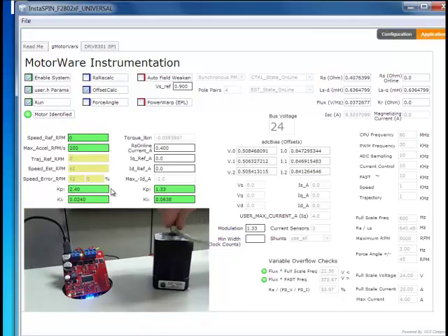At zero speed, you'll see that the motor isn't moving, or it's moving slightly, but it is trying to control zero speed, meaning when it sees a directional acceleration, it fights back based on the tuning of the speed controller, either aggressively or softly. So it's not too bad there, but it's also not great. We could stiffen this up. But what's fun to do here is actually look at the behavior of your P and your I term. We can tune these way down.